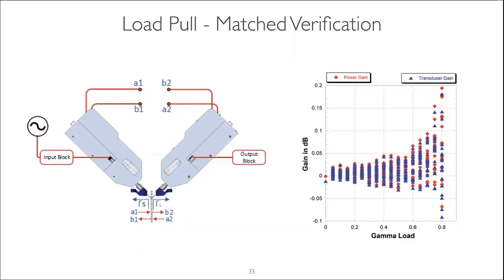Here, and these are actually one of the first measurements we're doing, now we've been tweaking some calibrations and optimizing a few things, but this is the kind of match verification we should expect at a minimum. Here the worst case is about 0.2 dB at 0.8 gamma. So now you know that when you get performance like that, your S parameter measurements are good, your tuner calibrations are good, and all the de-embedding is right. And this is the kind of performance you should expect from a system like this.